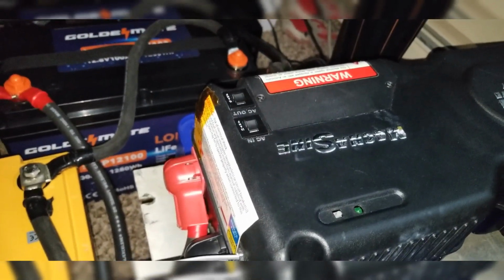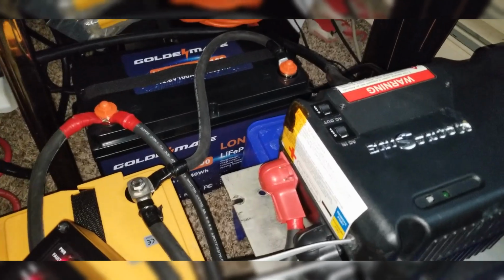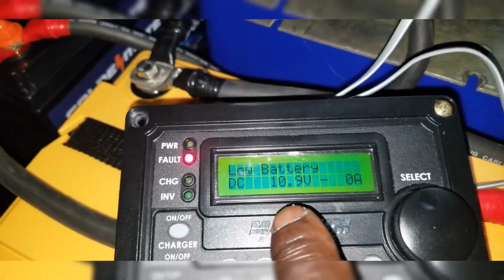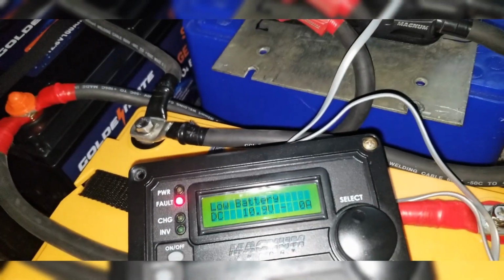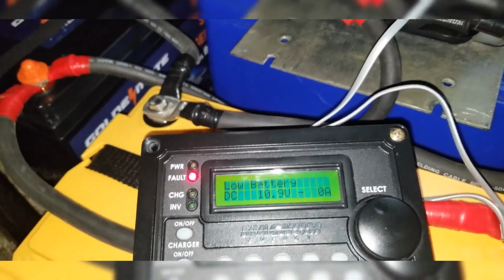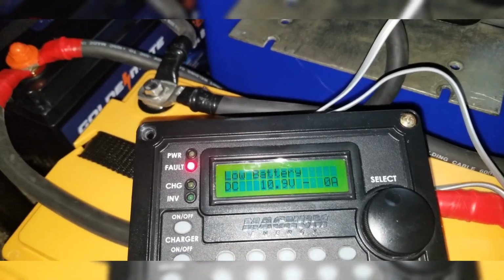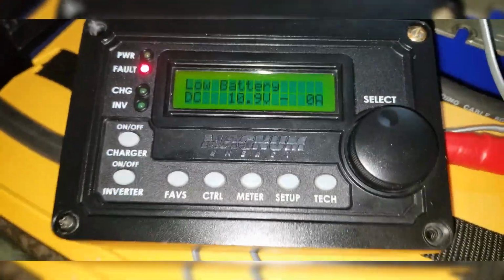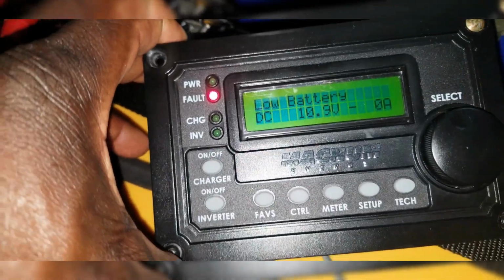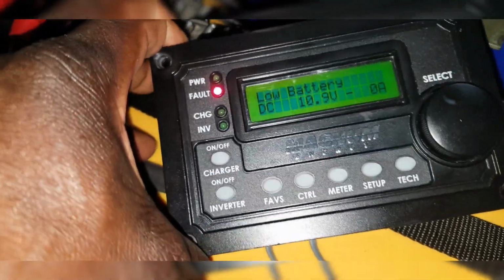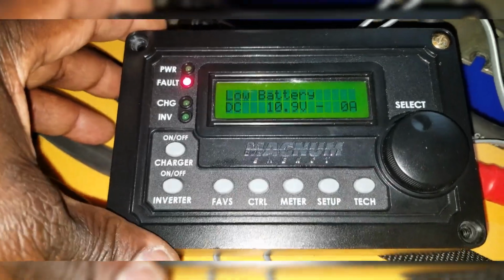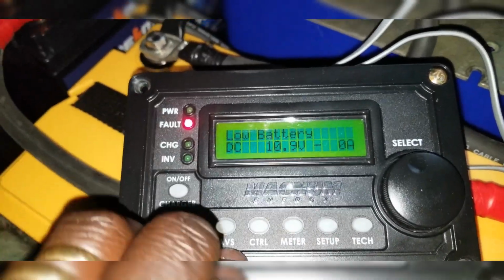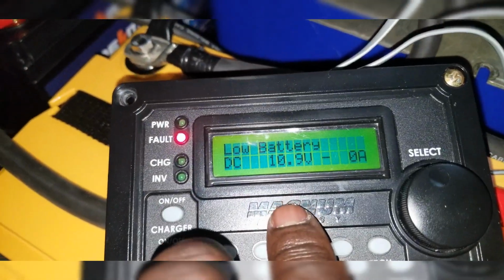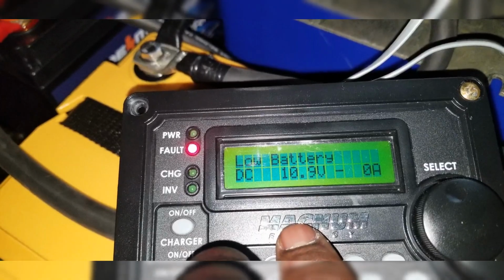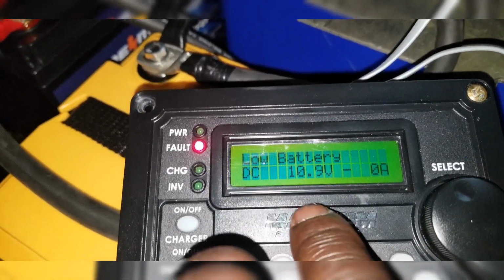So 120-something, 128 for example, multiply that by the voltage you saw here at that time, that 11 point something or whatever, and see how many watt-hours were coming out of this inverter, the surge. That's why I simulated it for you guys, to see exactly what I'm talking about. It holds the surge for quite a while at 100-some amps, and the voltage is not available anymore on the batteries, and now the system shut off.